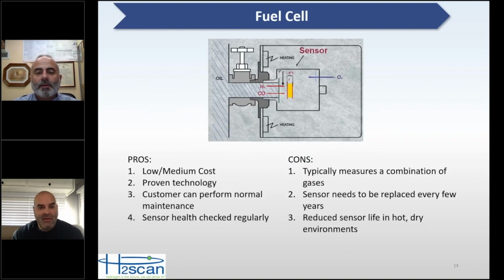So with the fuel cell sensor, you've got some type of membrane. Fuel cell can't survive directly in the transformer oil, so you have to separate the gas from the oil. Typically, most of the fuel cell sensors out there, you have hydrogen and CO. You have newer ones that I'm not sure how they do it, but they are hydrogen-only monitors today. But in general, the principle is you separate the gas from the oil. So the gas migrates through a membrane, and that combustible gas provides fuel for the fuel cell. They look at the voltage output of that fuel cell, and they're able to correlate that to a gas number for gas analysis in your transformer, and by watching that trend, you're able to tell if there's an active problem in the transformer.